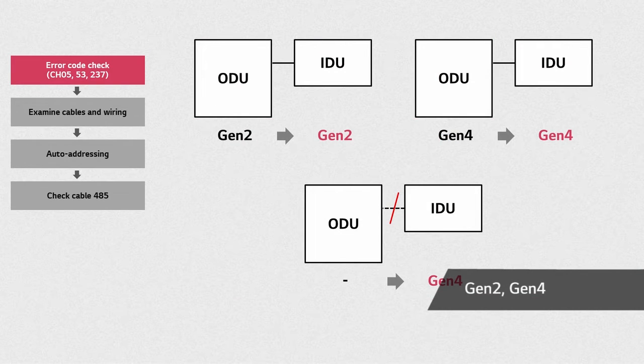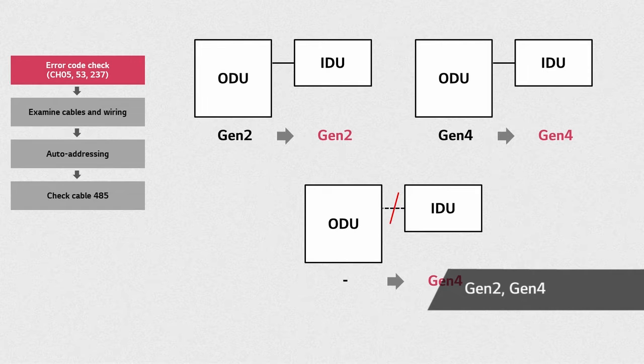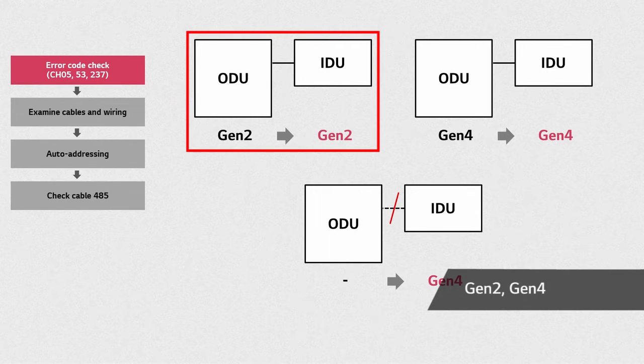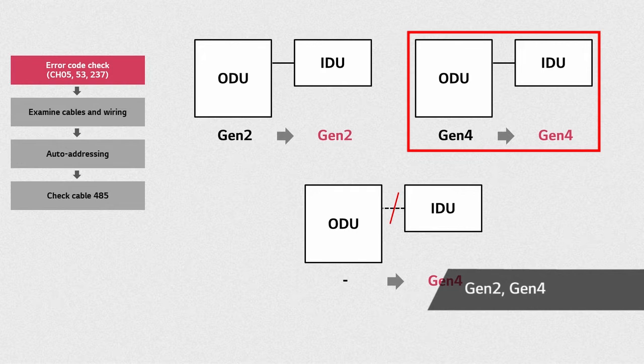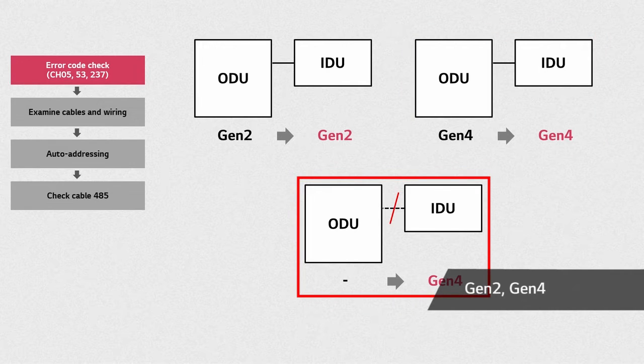The indoor unit will be initially set to Gen4, and after communication with the outdoor unit starts, the indoor unit's communication mode will be adapted and reprogrammed according to the state of the outdoor unit. If the outdoor unit is set for Gen2, the indoor unit will be set for Gen2 as well, and if the outdoor unit is set for Gen4, the indoor unit will adopt Gen4 mode. If there is no communication between IDU and ODU, the indoor unit will remain in Gen4 state regardless of the ODU communication mode.